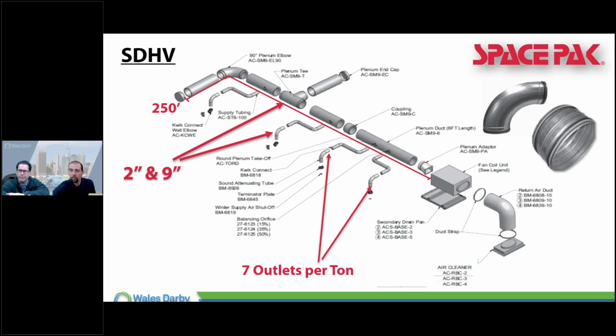The return, like Rick mentioned, is kind of fixed to make sure we have enough CFM to get back to that coil, so we don't starve it and ice it up. You can make your own, be creative, make more than one if you choose to. But really, in our world, because we pressurize and throw the air, one return is more than enough if it's sized properly.